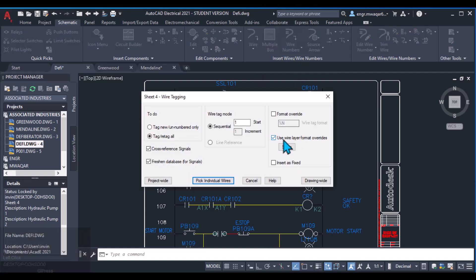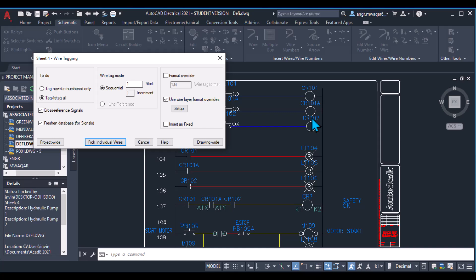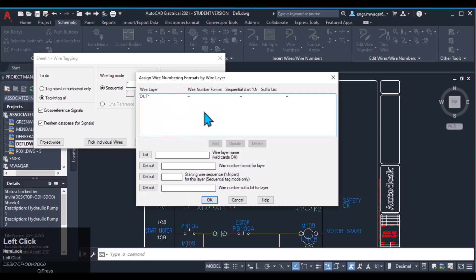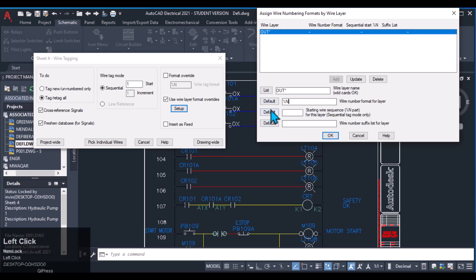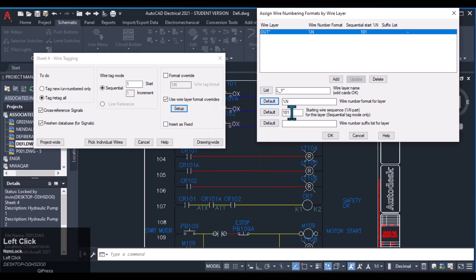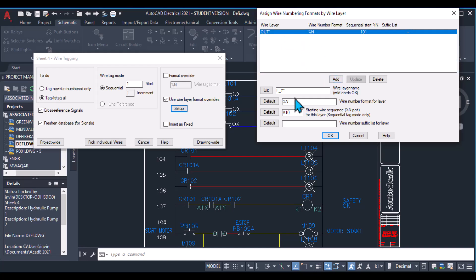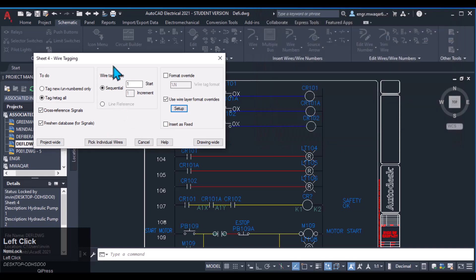Re-tagging is important because the wire reference numbers change when rungs move. Whenever we create different wire layers, we use Wire Layer Format Overrides. This allows us to assign wire numbers in different formats for different wire layers. For example, for one layer I will use the default format percent-N starting at 101 and click Update. For another layer called L-Y, I want to assign the number format A10, so I add that wire layer to the list and click Update, then OK.